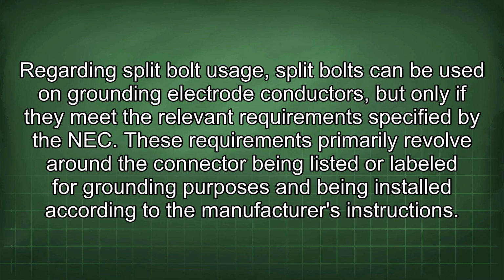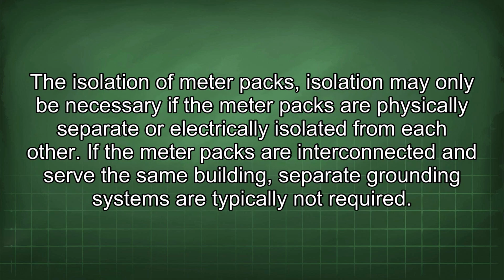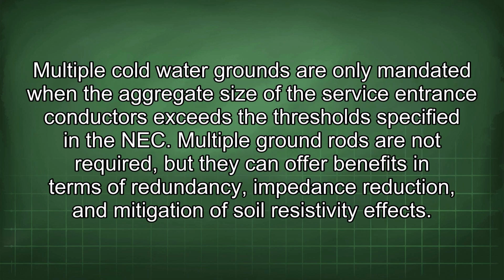These requirements primarily revolve around the connector being listed or labeled for grounding purposes and being installed according to the manufacturer's instructions. The isolation of meter packs. Isolation may only be necessary if the meter packs are physically separate or electrically isolated from each other. If the meter packs are interconnected and serve the same building, separate grounding systems are typically not required. Multiple cold water grounds are only mandated when the aggregate size of the service entrance conductors exceeds the thresholds specified in the NEC. Multiple ground rods are not required, but they can offer benefits in terms of redundancy, impedance reduction, and mitigation of soil resistivity effects.